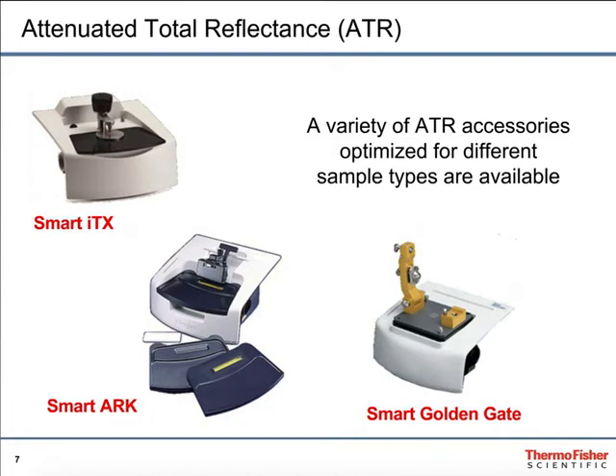There are a number of configurations of attenuated total reflectance accessories. The Smart ARK is what's called a multi-bounce, which means the IR beam bounces multiple times along the crystal, giving multiple interactions with the sample so that you get a longer path length in essence. The Smart ITX and the Smart Golden Gate are designed to be single bounce, meaning you only interact once with the sample. All three of these, and most of the other accessories, can be configured with different crystals — germanium, zinc selenide, or diamond — allowing you to tune your depth of penetration, the number of interactions, and the robustness to suit your environmental conditions.